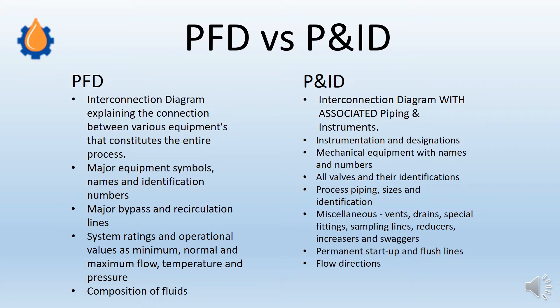Major bypass and recirculation lines that are part of the process are shown in the PFD, and later in the P&ID we do detailed engineering of these systems. System ratings and operational values — minimum, normal, and maximum flow, temperature, and pressure — are available in the PFD. The composition of the fluid, such as the constituents of crude oil or a gas like methane, is also available in the PFD.